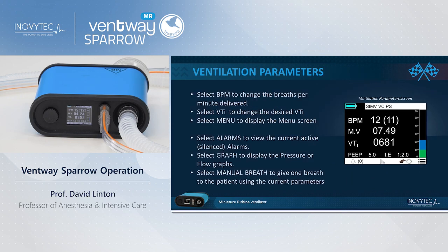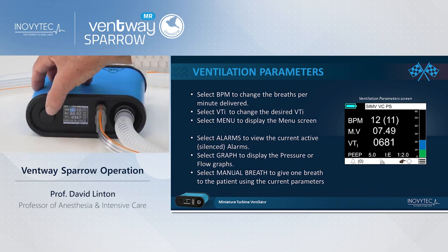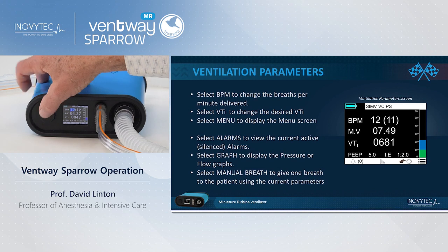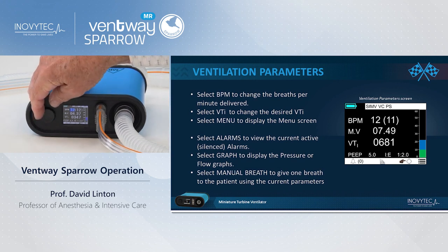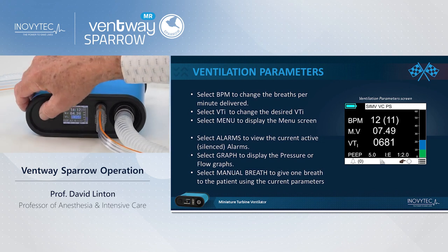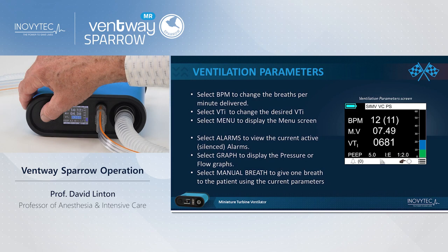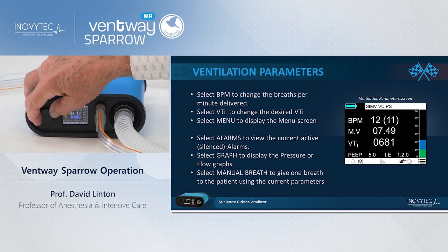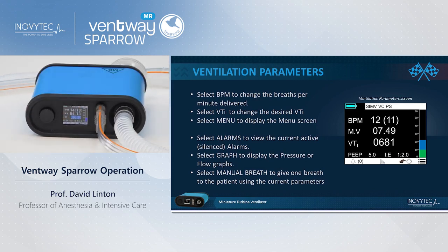If you as a physician select to increase or decrease the breaths per minute, you have to move the cursor to the breaths per minute, click on it, and then adjust the breaths per minute each way you want. I will go up to 14 breaths a minute. Similarly, you can change the tidal volume. At the moment it's 360. I'm going to make it 380.